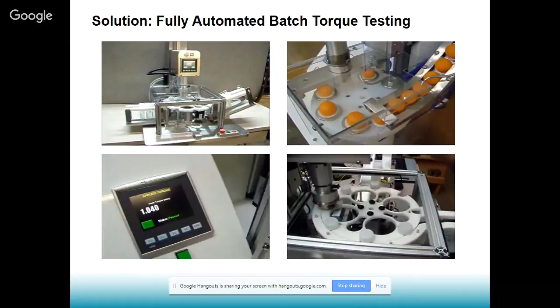And on the next slide, I wanted to briefly show you the potential issues in the pharmaceutical industry or field. We have run into applications when the customer wanted to test blood products, where it was a requirement to protect the operator from spills. And it is also a possibility, mostly in the beverage industry, especially with beer testing, when the bottle is glass and it's also pressurized. So if there's a micro crack or something and we do a torque test, there is a chance of the bottle breaking and some projectiles hitting an operator.